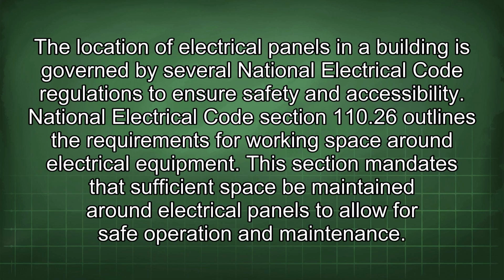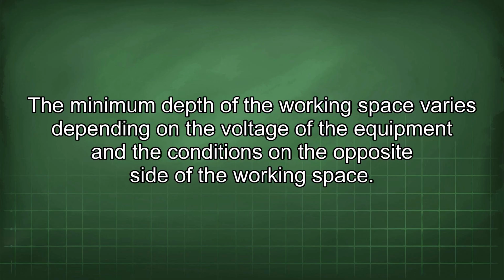The location of electrical panels in a building is governed by several national electrical code regulations to ensure safety and accessibility. National Electrical Code Section 110.26 outlines the requirements for working space around electrical equipment. This section mandates that sufficient space be maintained around electrical panels to allow for safe operation and maintenance. The minimum depth of the working space varies depending on the voltage of the equipment and the conditions on the opposite side of the working space.